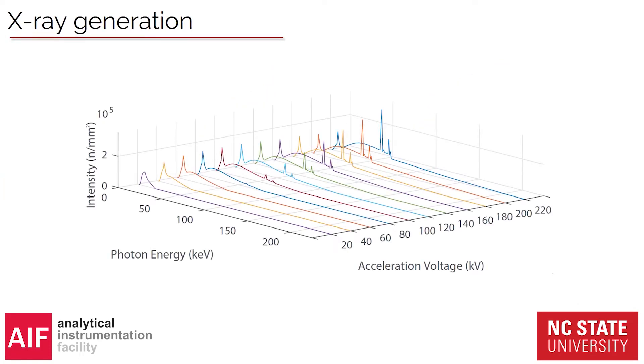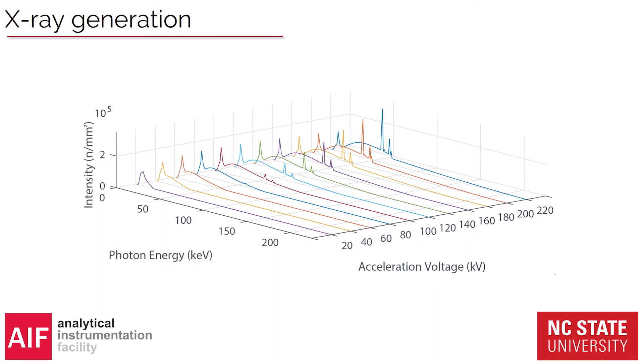This is the spectrum you get from a tungsten target, which I think is most common. You can use other materials like copper and molybdenum — there are different target materials depending on what you're intending to scan. Here you can see how the photon energy depends on the acceleration voltage of the electrons. You can see that long tail which is the Bremsstrahlung, and the peaks which are the characteristic X-rays. This is both good and bad — we will discuss that later.